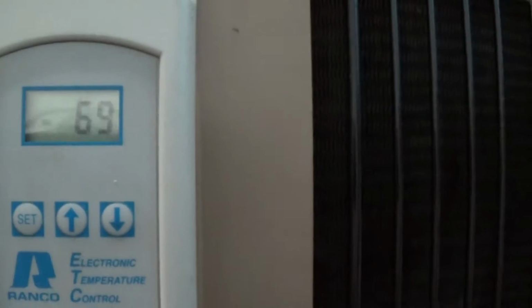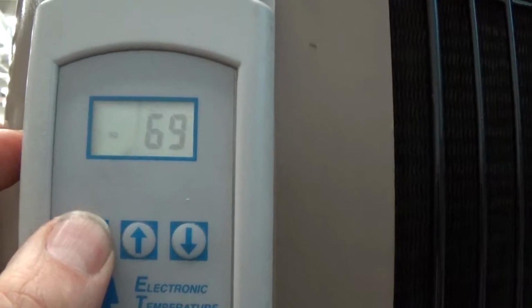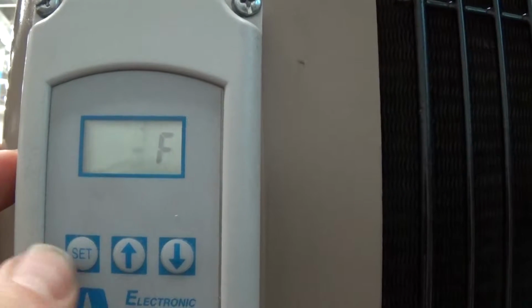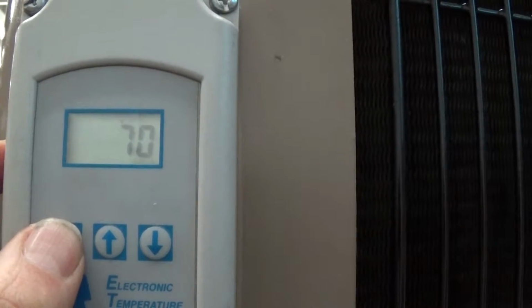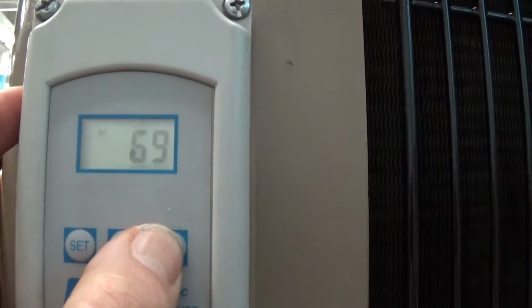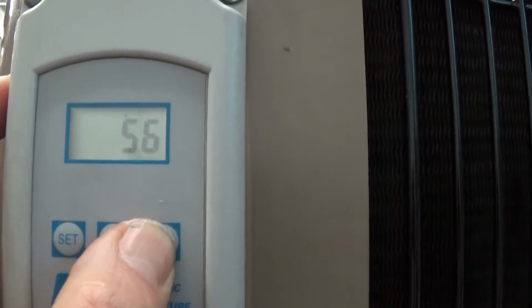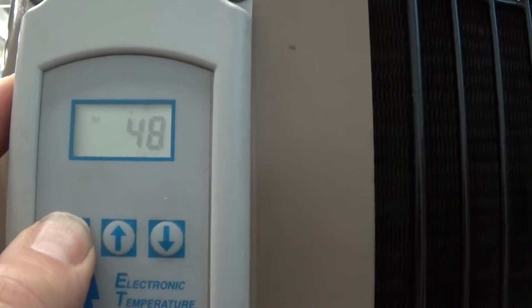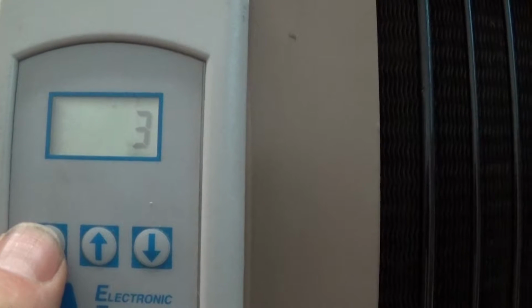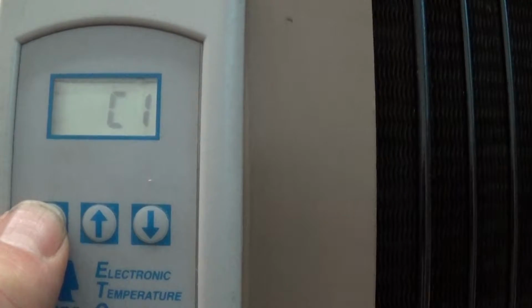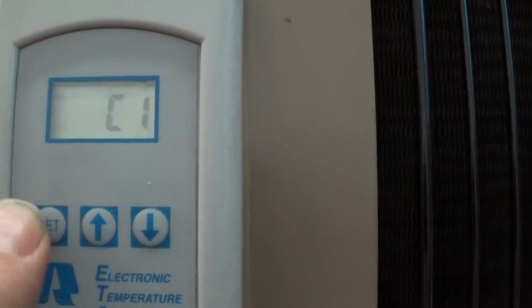So right now, whenever you come up to this Ranco screen here, that's going to show you what the temperature of the fluid is running at currently. There are 2 set points in here, so we're going to change this and run this down to 48 degrees today. So the first thing you do is you press set. That tells us that set point 1's in Fahrenheit. Press set again. That tells us that the set point's 70. We're going to bring that down to 48. And press set again. That tells us we have a differential of 3. Leave it at 3, that's okay. Then you press set again, cooling mode 1, and for set point 1 that's what you want, leave that there.